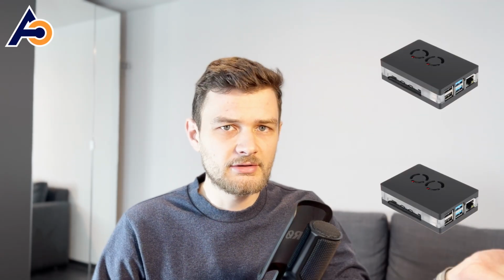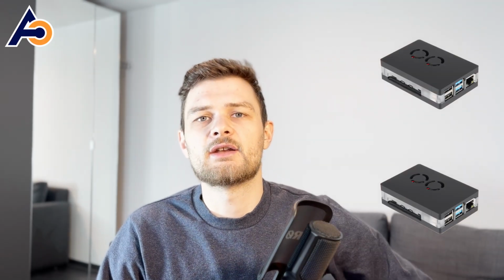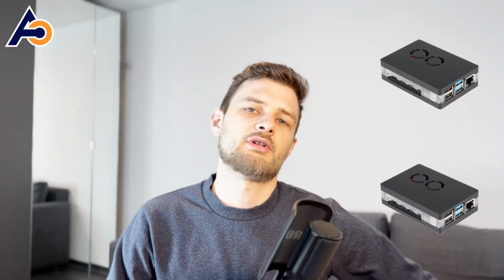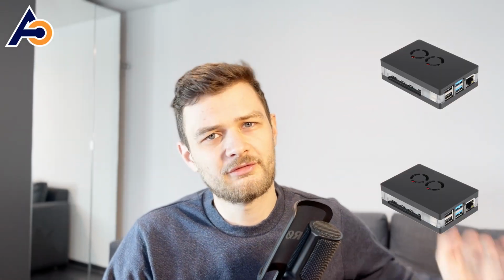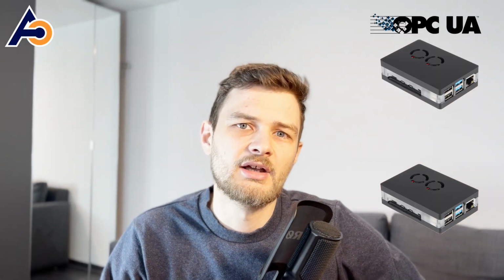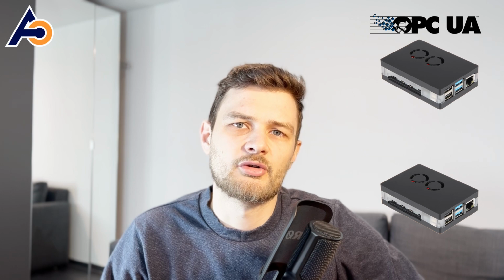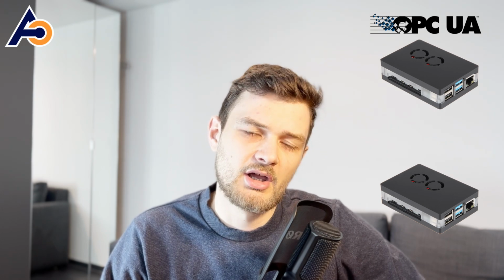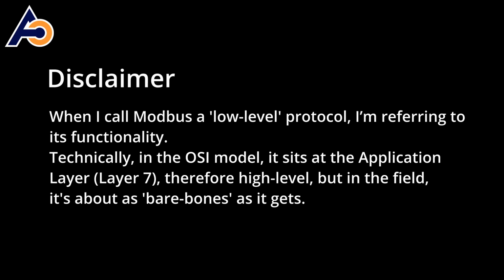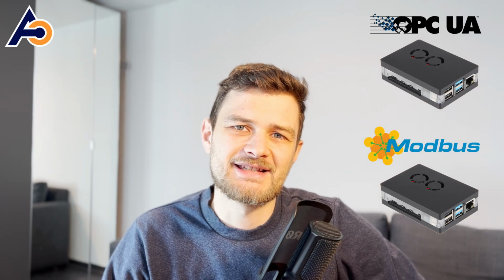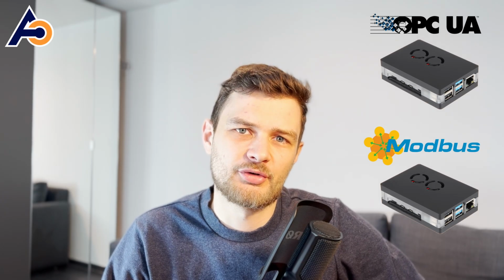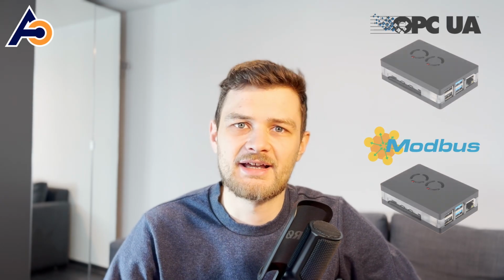We will use two similar devices and we will integrate them into my monitoring system. The catch, of course: one of these devices runs OPC UA and the other one runs the low-level protocol Modbus TCP. When I call Modbus a low-level protocol, I'm referring to its functionality. Technically, in the OSI model, it sits in the application layer, therefore high level, but in the field, it's about as bare bones as it gets. Modbus TCP basically stands for all the other low-level protocols, FANUC FOCAS, Beckhoff ADS, and so on.